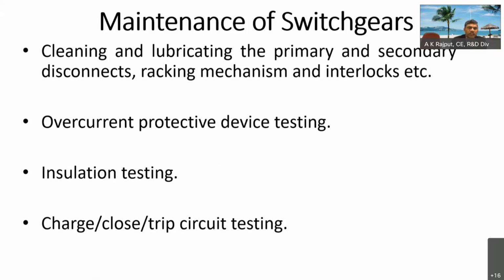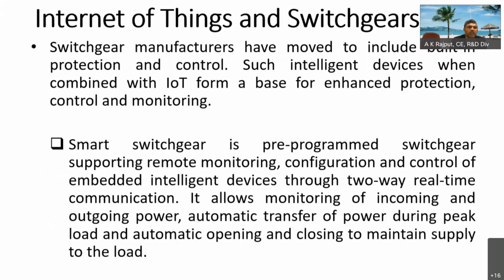So in the maintenance cell, you will be doing the lubricating, primary and secondary disconnection, racking mechanism, and the interlocks; you will check whether they are functioning or not. Overcurrent protective devices will be tested, insulation testing will be done, and spring charging mechanism, closing and trip circuit testing will be done, whether they are continuous or not, and whether they are getting a healthy supply or not. The fuses will also be checked properly. So these are the things.